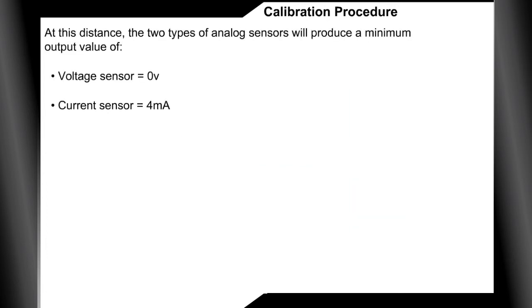At this distance, the voltage sensor will produce a minimum output value of 0 volts, and the current sensor will produce a minimum output value of 4 milliamps.